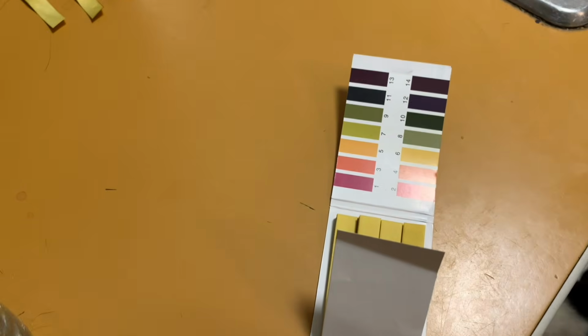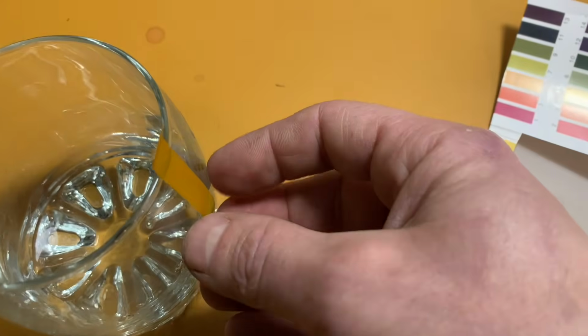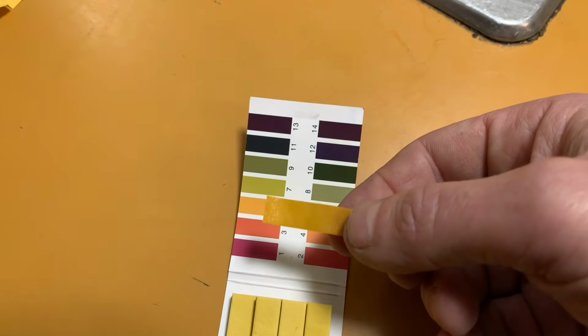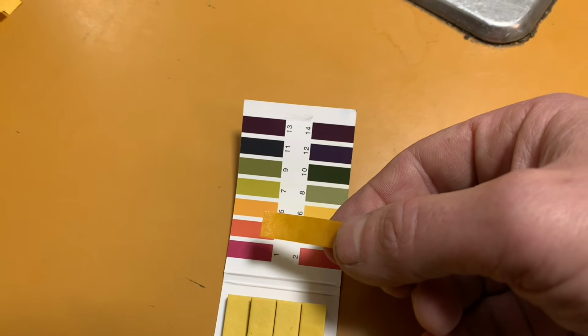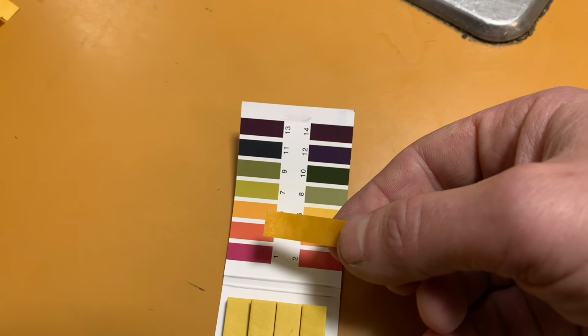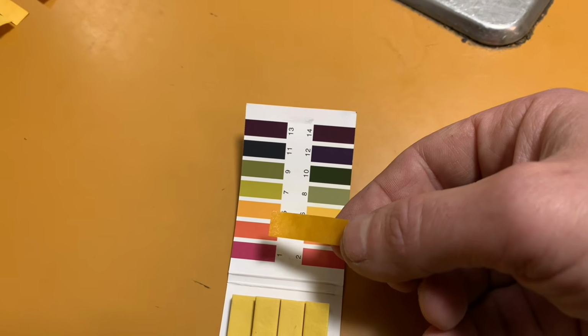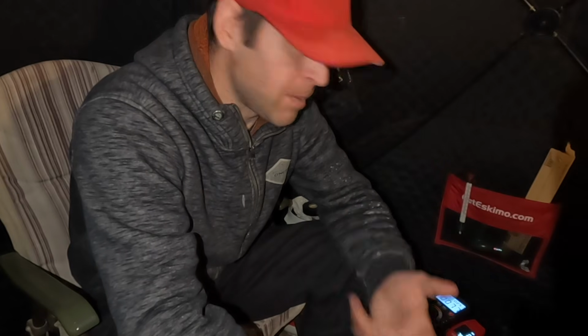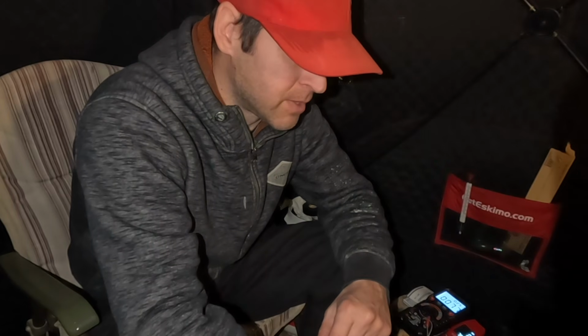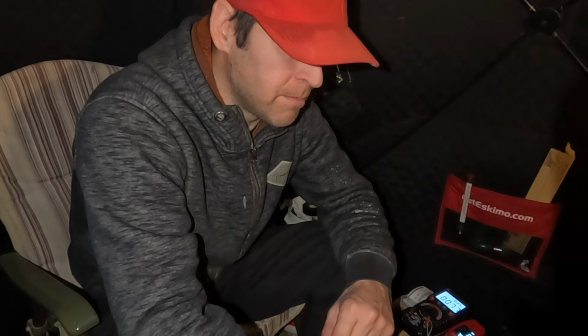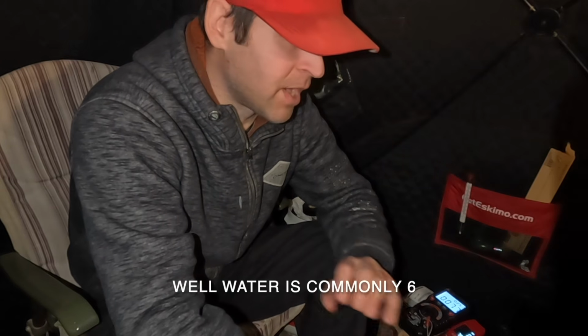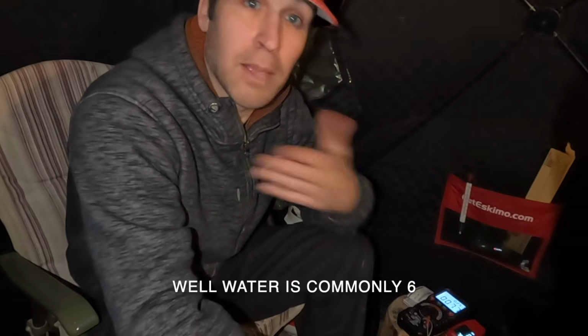That's the one strip. Let me get the other strip here, just to make sure they're the same. Yeah, as you guys can see, somewhere in between there, around a 5 - I'd call it a 5. Copper, as far as I know, has pretty good corrosion resistance, maybe just because it builds up oxides, but yeah, I'm definitely not worried about a pH of 5 damaging the exchanger. Let me know if I should be.